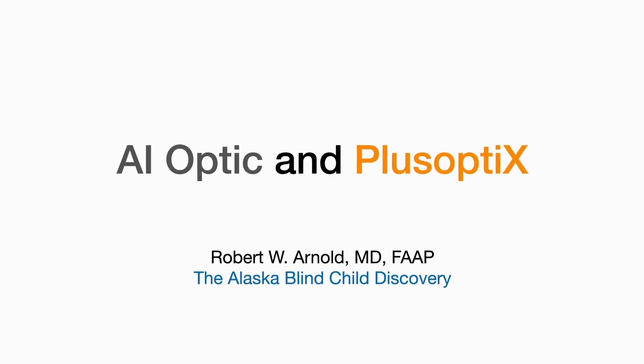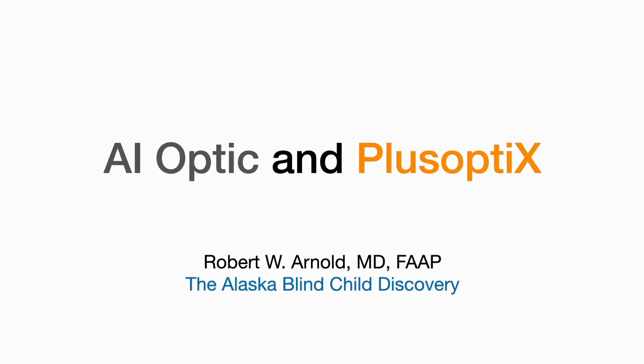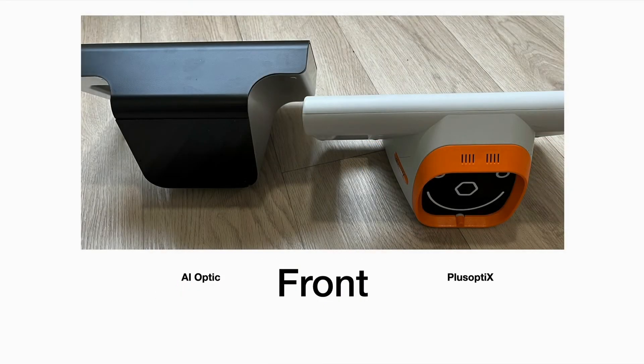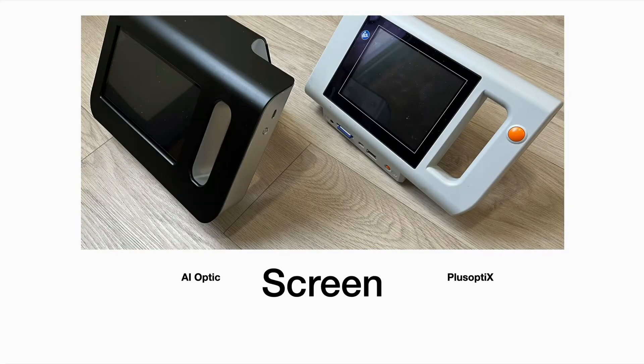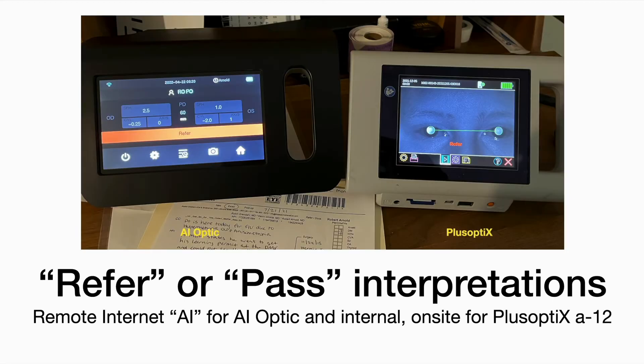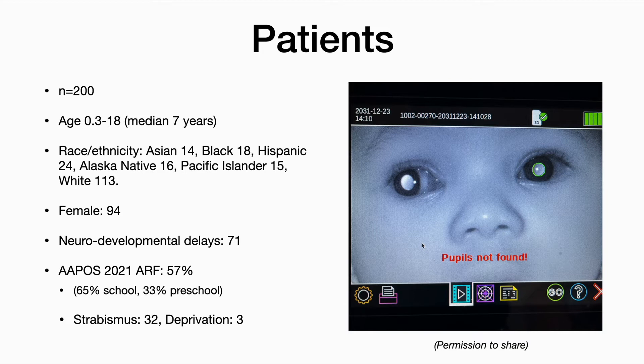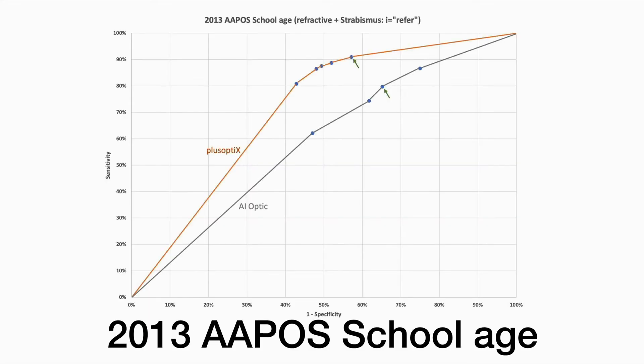This is a comparative validation project comparing the brand new AI Optic with the conventional PlusoptiX a-12 photo screeners. We studied 200 patients, average age 7, with wide ethnic diversity and several with neurodevelopmental delays, but they had a high amblyopia risk factor prevalence. We used receiver operating characteristic curves, or ROC curves, to compare the ability to detect amblyopia risk factors by the PlusoptiX in orange and the AI Optic in gray. This is based on the 2013 AAPOS uniform guidelines for refractive plus strabismic.